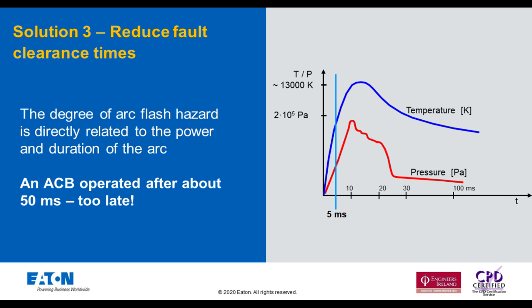If we're able to stop the effects of the arc in 5 milliseconds or less, the problem is much less severe due to the log scale, as the pressure and temperatures will be reduced. So what technologies are around to help us reduce this arc duration time? This is where we use the implementation of arc quenching technology, which I'll discuss a little bit further now.